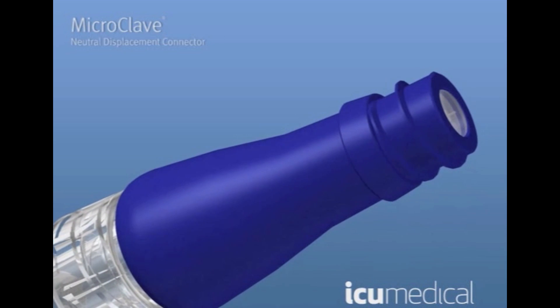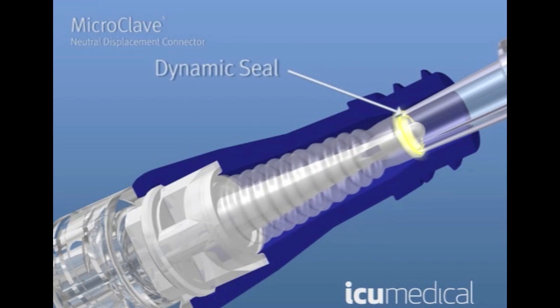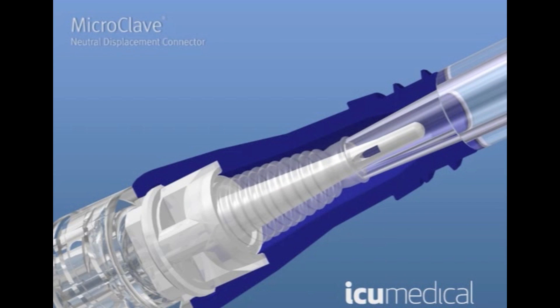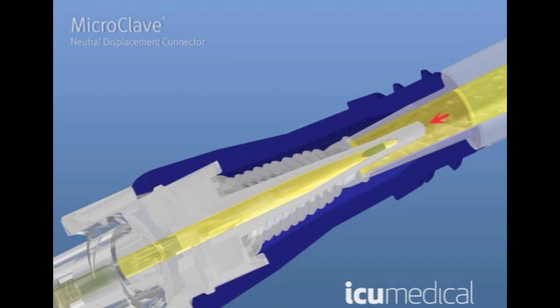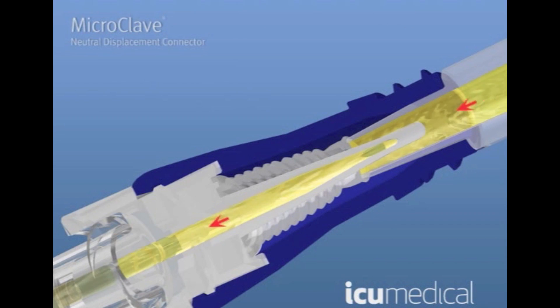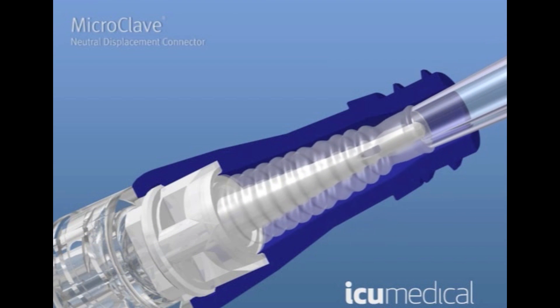As the access luer contacts the sterile silicone surface and begins to compress the septum, a dynamic seal is created and the internal blunt cannula begins to pass through the split septum. Not until the silicone is compressed and the windows of the cannula become exposed in the internal diameter of the access luer is the fluid path accessed. This creates the dedicated internal fluid path, where at no point does the exterior of the access luer, split septum, or housing come in contact with the fluid path. When the access luer is removed, the septum returns to cover the cannula and closes the fluid path once again.